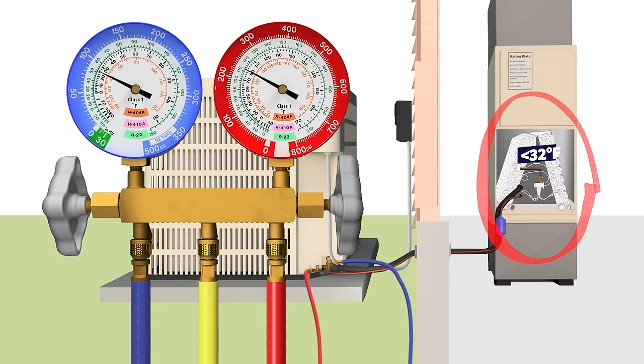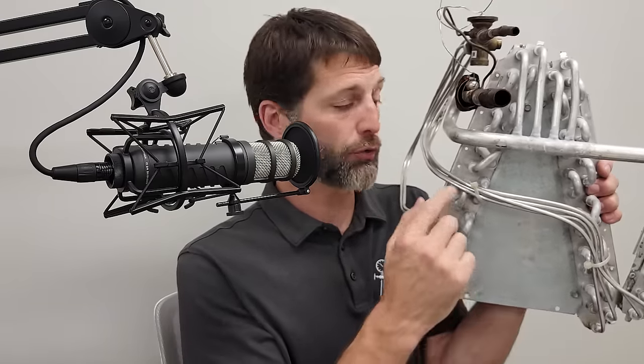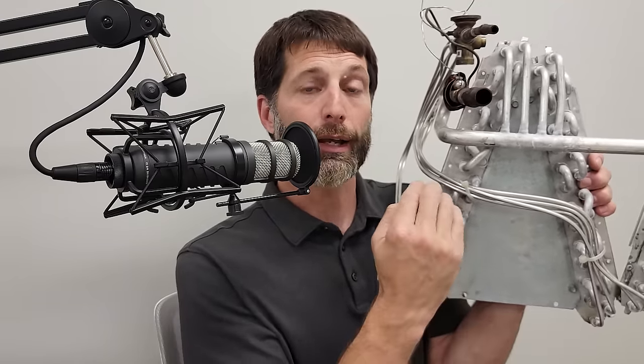It's not the refrigerant itself that's freezing. The refrigerant is just below 32°F, which is the temperature at which water freezes. Any air traveling across this coil gets attracted to that low temperature tube, condenses, and then immediately freezes onto the coil.